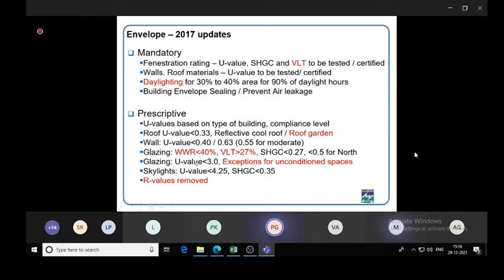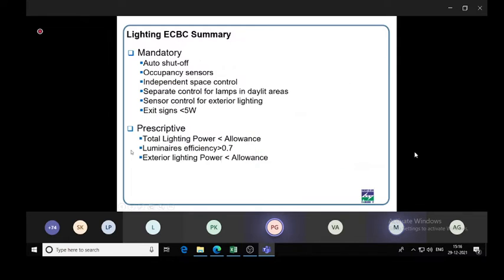U value should be less than 3. And skylights again. In terms of lighting, the mandatory requirements are automatic timer or occupancy controls, occupancy sensors for specific types of spaces like conference rooms, toilets, etc. Then additional controls are required for daylight areas. Then we have the LPD requirement under the prescriptive section, lighting power density.